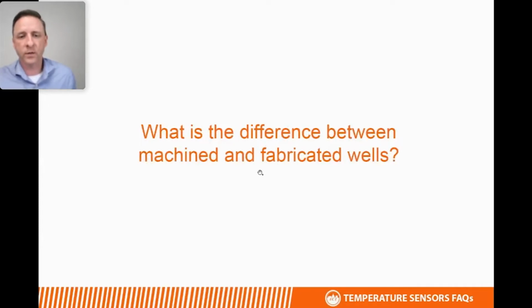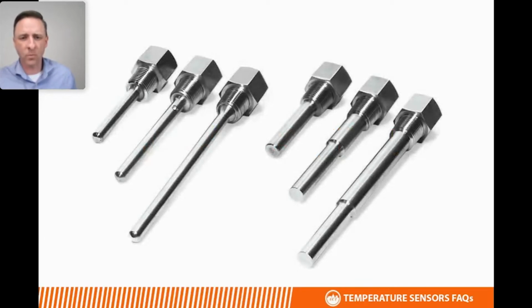That leads to the next question: what's the difference between the machined and the fabricated wells? I'll go back to this picture to show you that the fabricated wells are made of 2 pieces of stainless steel that are welded together. There's a weld inside of the female thread, whereas the machined wells are cut out of one solid piece of stainless steel. And as mentioned, the fabricated wells are the default or standard well that comes with our immersion sensors, and those are included with our standard part numbers.